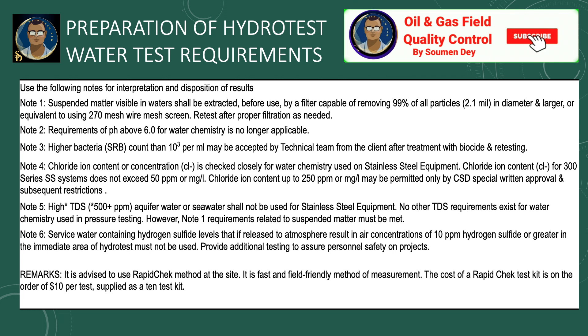Service water containing hydrogen sulfide levels that, if released to atmosphere, result in an air concentration of 10 ppm or greater in the immediate area of the hydrotest must not be used. It is advised to use the rapid check method at the site — it is a fast and field-friendly method of measurement. The cost of a rapid check test kit is on the order of approximately $10 per test, supplied as a 10-test kit. Note that there might be other types of kits available in your area.